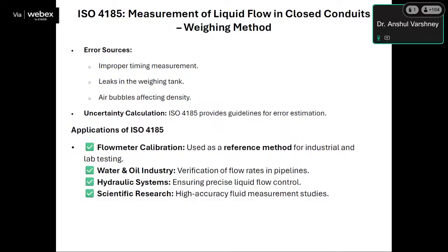ISO 4064 provides the guideline for installation requirements for water meters. As per ISO 4185, there are some error sources like improper timing measurement, leaks in the weighing tank, and bubbles affecting density. For uncertainty calculation, ISO 4185 provides guidelines for error estimation. The application of ISO 4185 is that it is used as a reference method for industrial and lab testing. It is used for verification of flow rates in pipelines. It ensures precise liquid flow control and high accuracy fluid measurement. It helps in high accuracy fluid measurement studies.